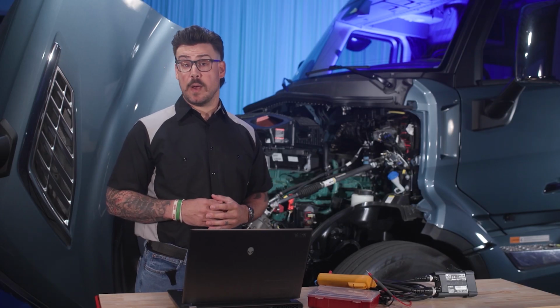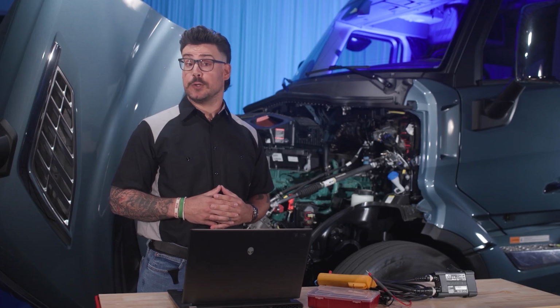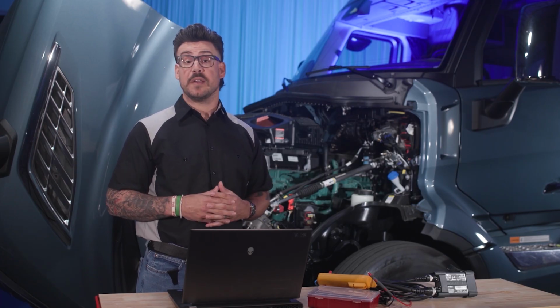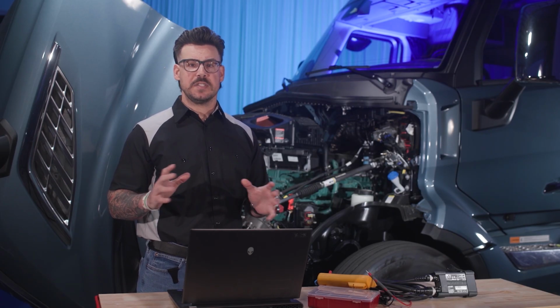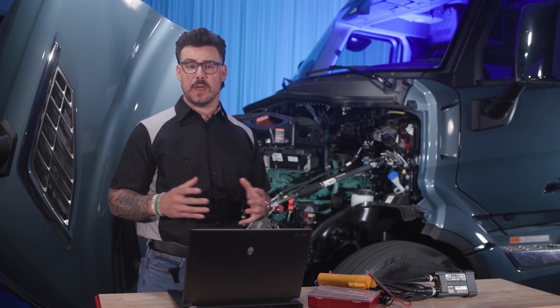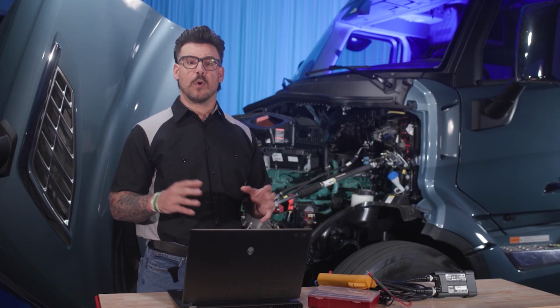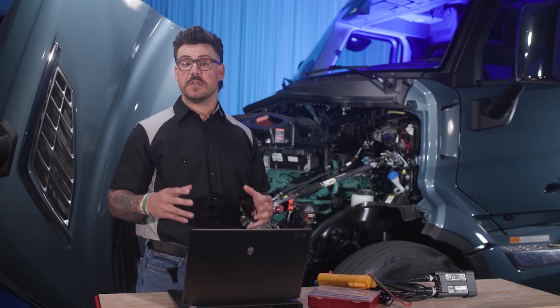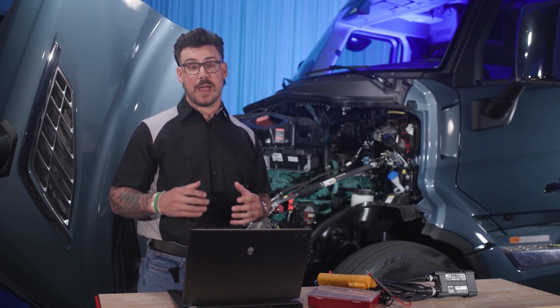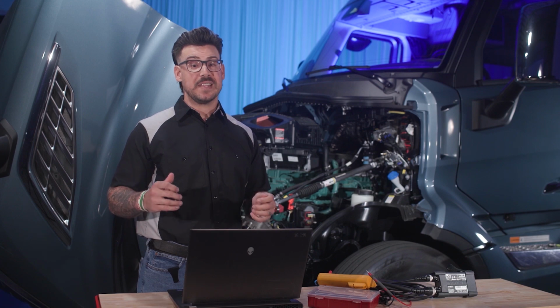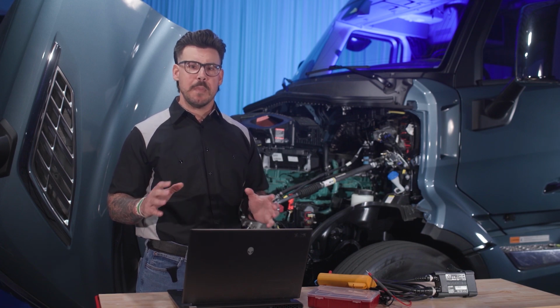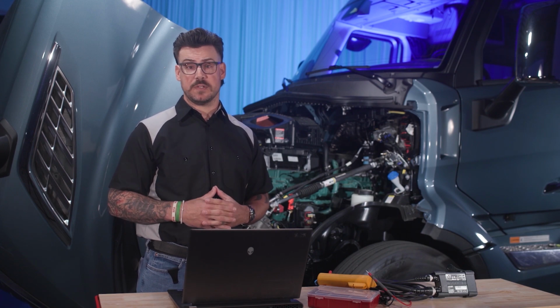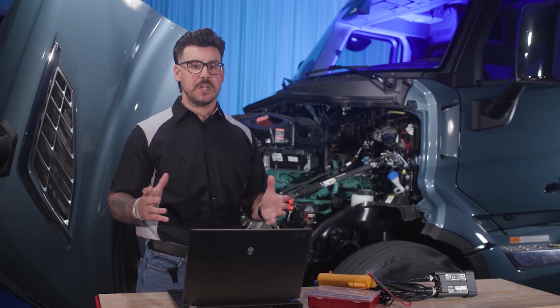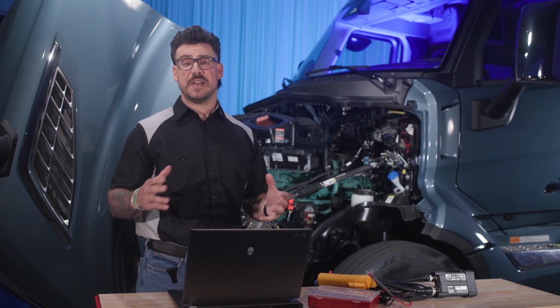Something we're seeing a lot of right now are multimeter readings that look good but don't line up with what the truck is actually doing. This depends greatly on the make and model of the multimeter you're using. For example, most of the time the meter is set to min-max and it feels like you're capturing the full signal, but that's not what's really happening. In many cases, the meter is averaging parts of the waveform. So what you're seeing isn't wrong, it's just not complete.